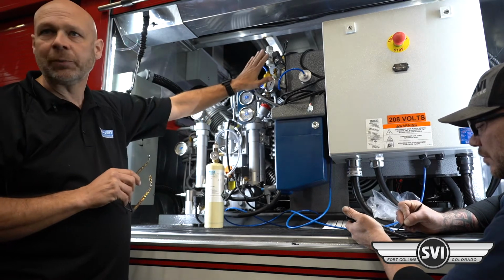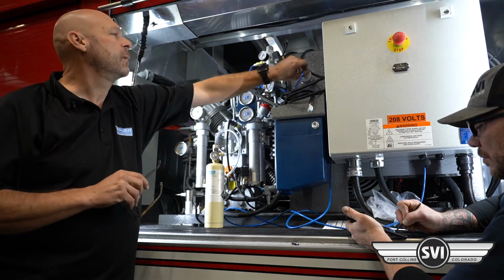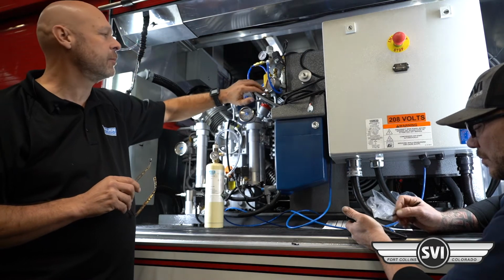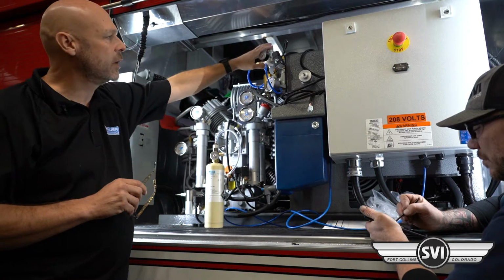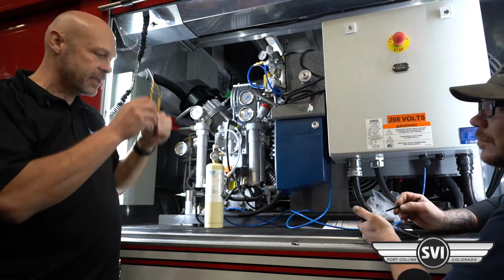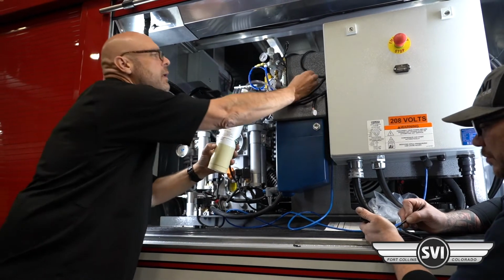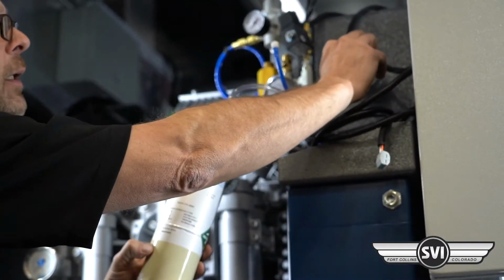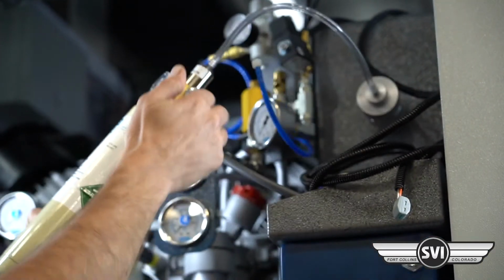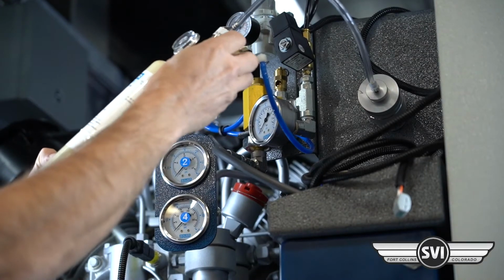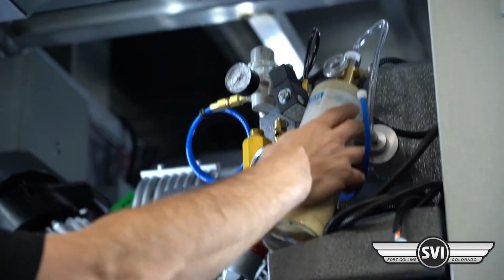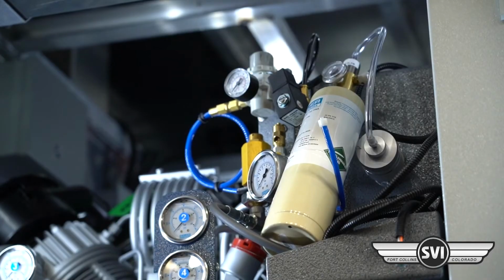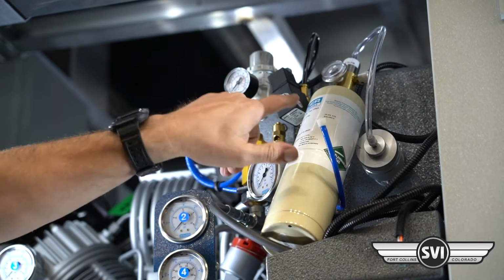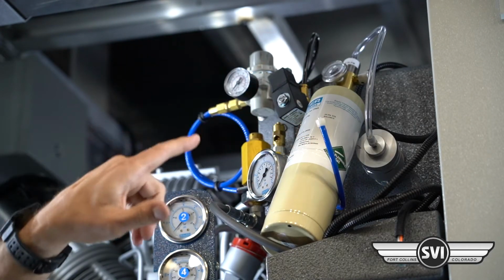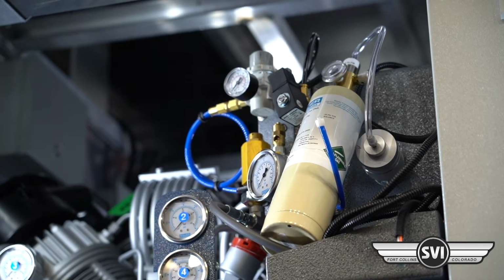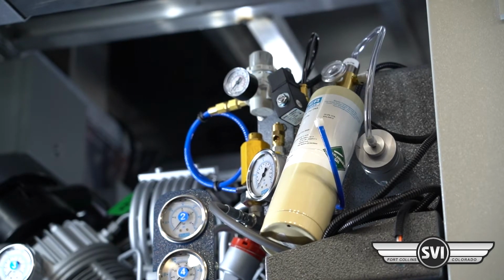So the regulator should be at 0. Actually, this one may read some because it's high pressure, but your regulator will be at 0. You disconnect the sample hose. This is just a quarter turn connection. That just quarter turns on, and then you open up the cylinder, at least one full turn, and then you can set that there. We're now flowing 0 gas into the sensor. So then we'll go back to the screen and we'll finish off the procedure.